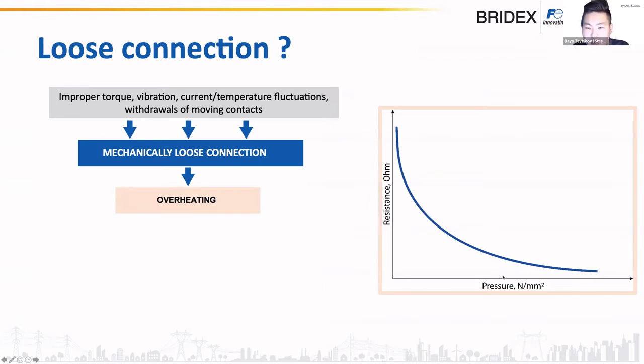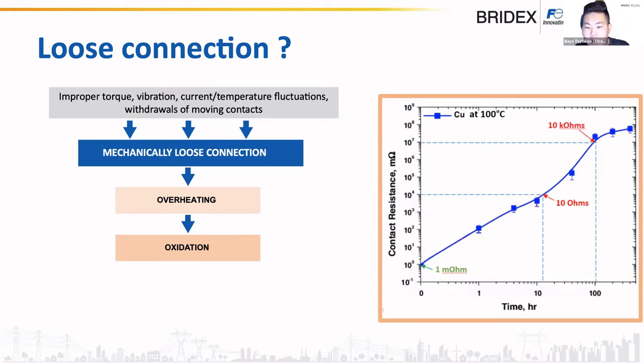As you can see from the graph here, the higher the pressure is, the lower the resistance is. But because we have a mechanically loose connection, the pressure is lower and the resistance increases. And this increase of resistance provokes overheating because of the Joule-Lenz law, which everybody knows. And this overheating provokes oxidation, because oxidation happens faster and much stronger at high temperatures.